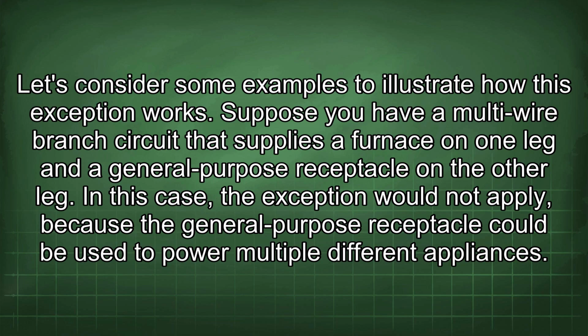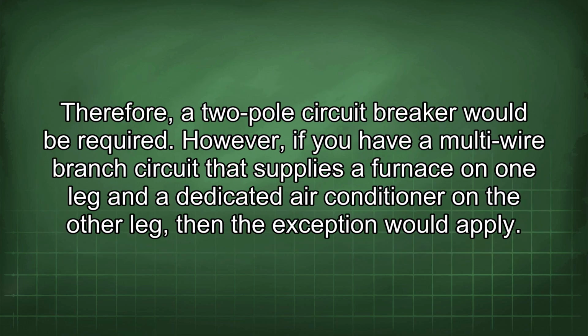Suppose you have a multi-wire branch circuit that supplies a furnace on one leg and a general-purpose receptacle on the other leg. In this case, the exception would not apply because the general-purpose receptacle could be used to power multiple different appliances. Therefore, a 2-pole circuit breaker would be required.